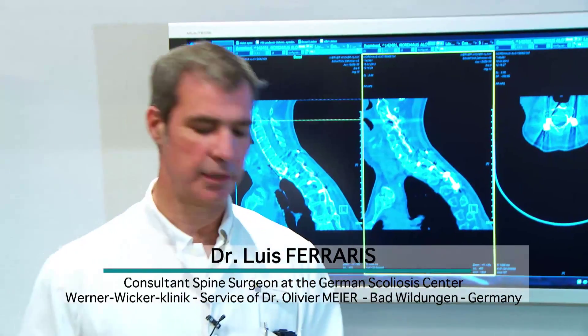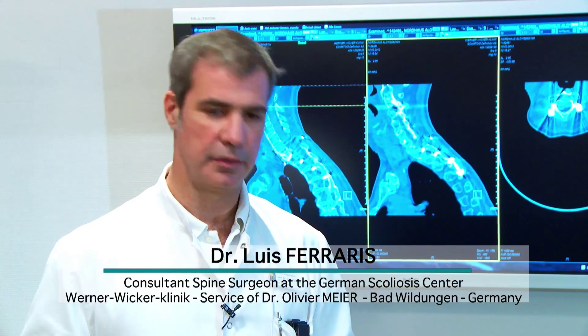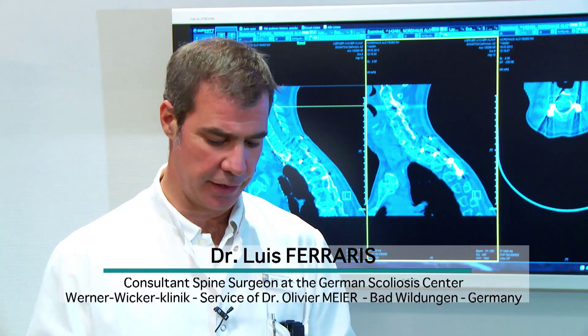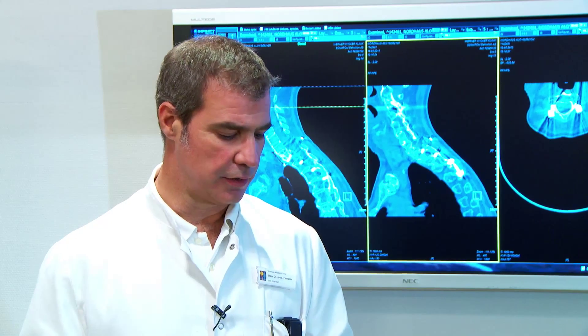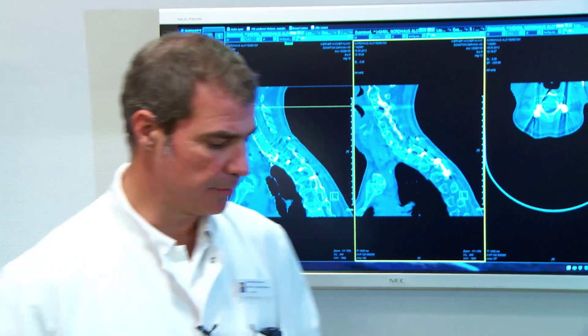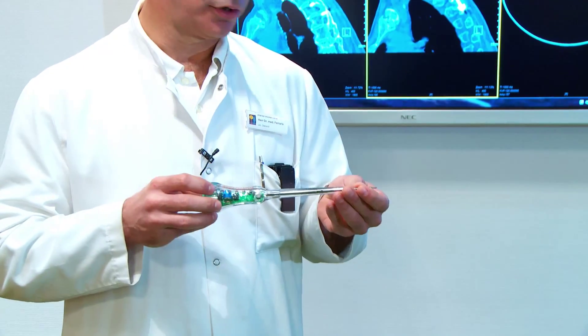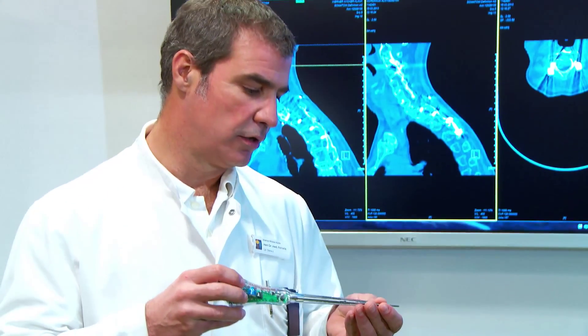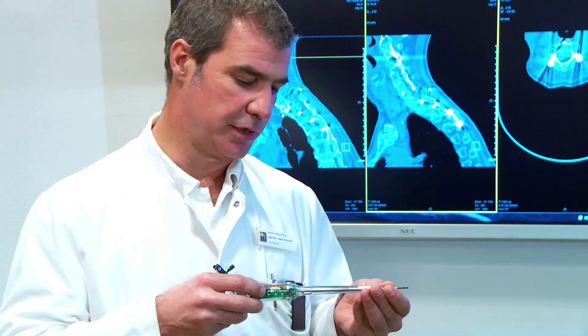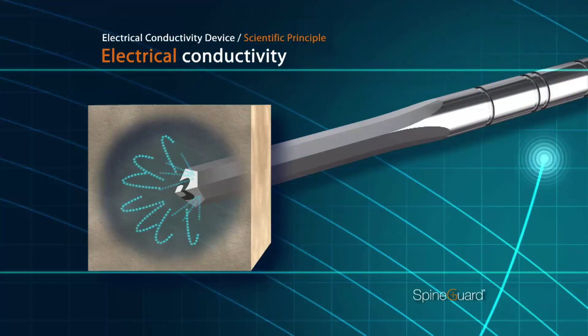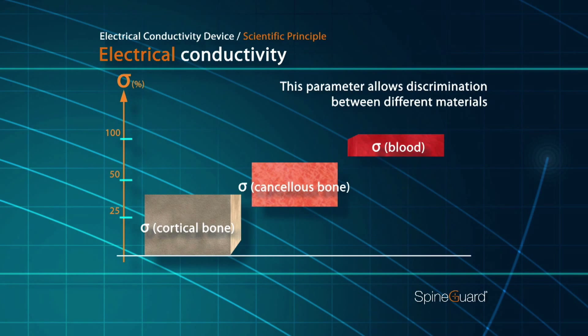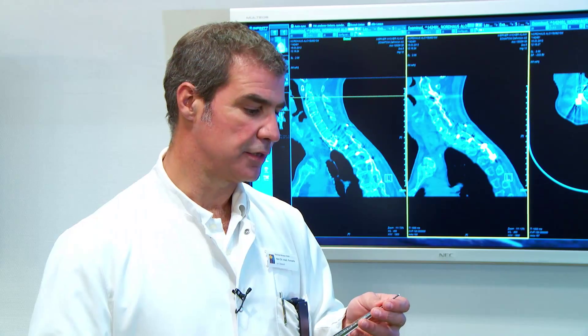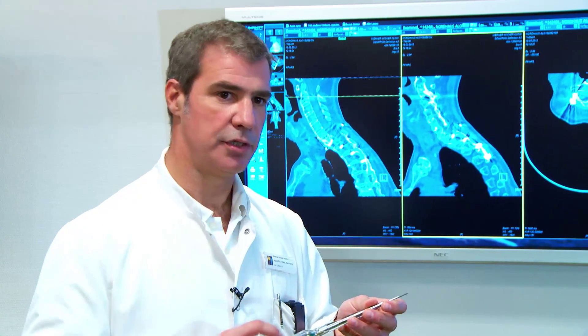The big advantage of PediGuard compared to other navigation systems is that it's very easy to use. The learning curve is quite short. You get real-time information about where you are in the bone, thanks to the conductivity system which allows you to know if you are in cortical or cancellous bone, or even if you're making a breach. The conductivity of cortical bone is not as high as cancellous bone, and even higher is the conductivity of fluids. That's why we have the beep tone coming from the PediGuard.